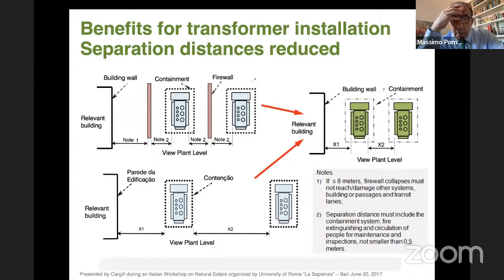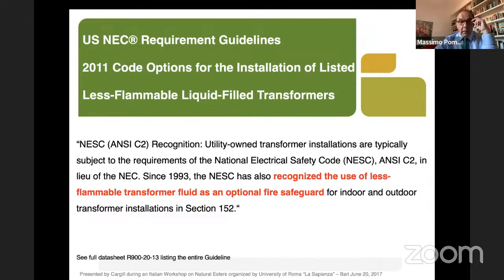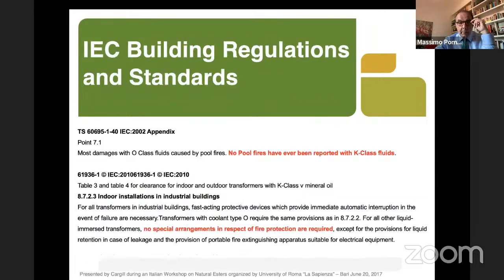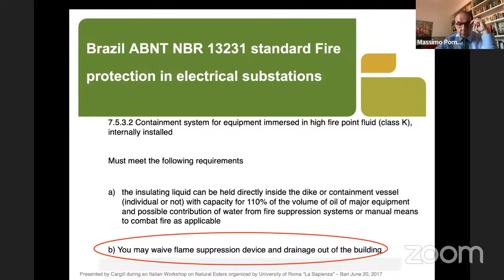So you can also see visually how this reduction works. On the left side is the situation with mineral oil, and in green on the right side is the situation with a natural ester transformer. There are no numbers here because the value depends on the quantity of mineral oil used in your transformer. I don't want to go into the specific requirements present in some standards, so let's move on.